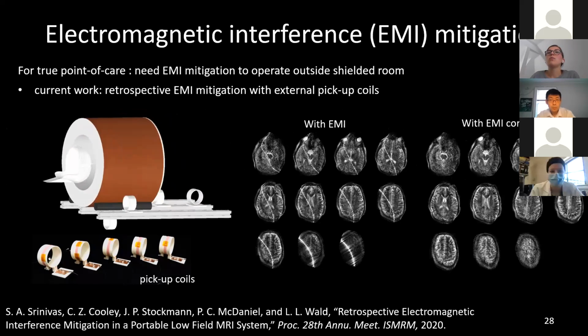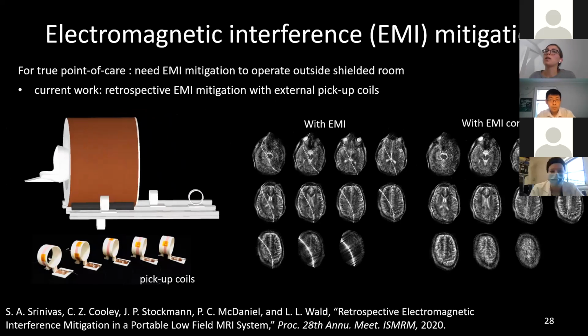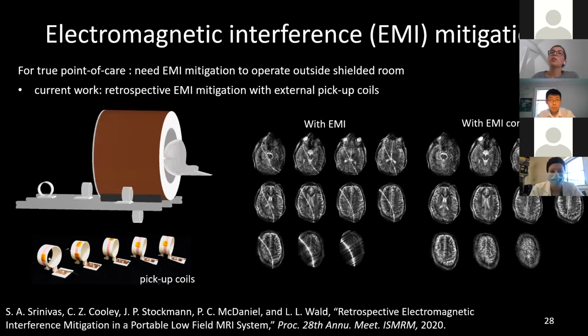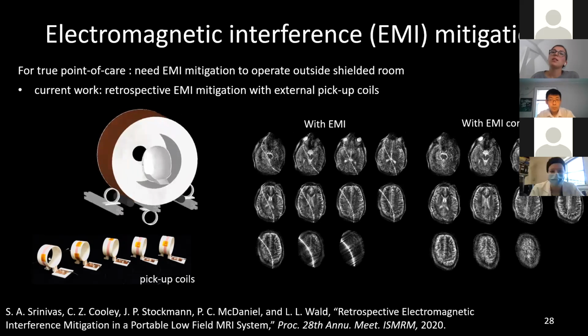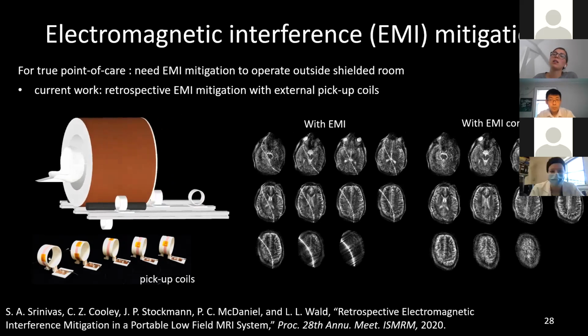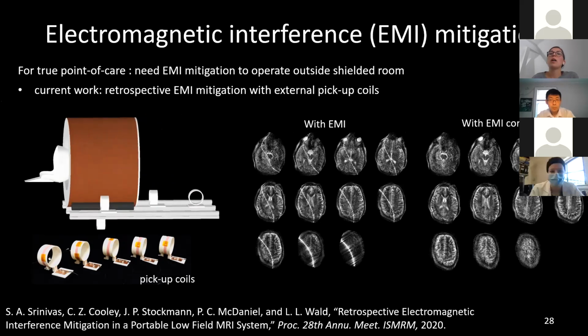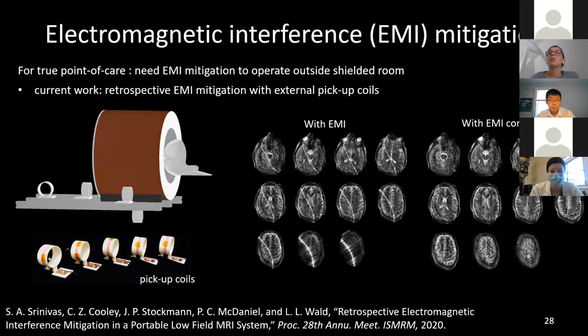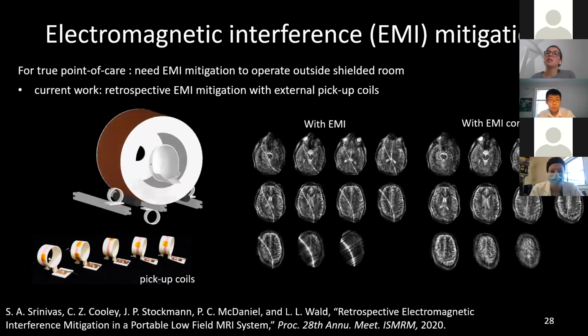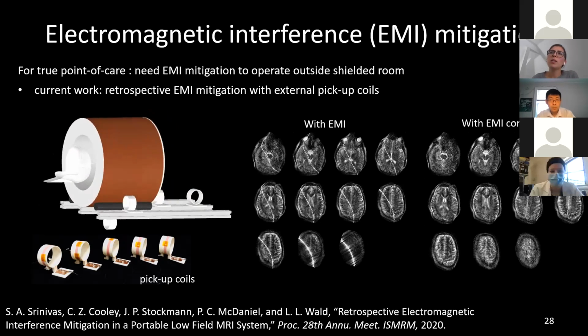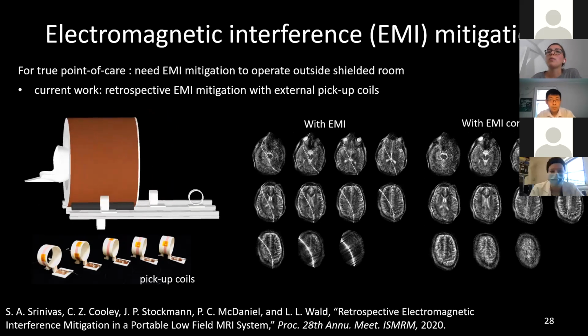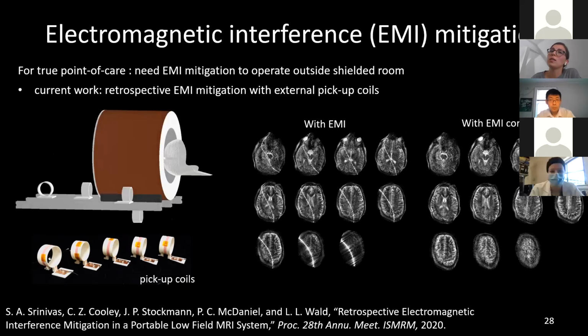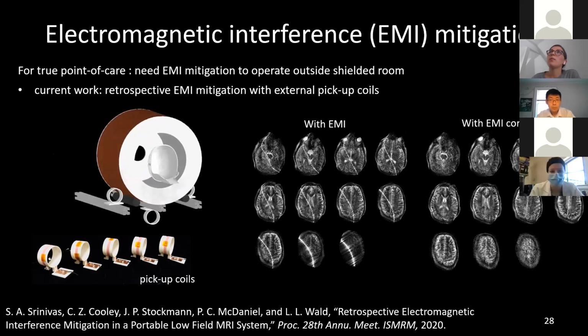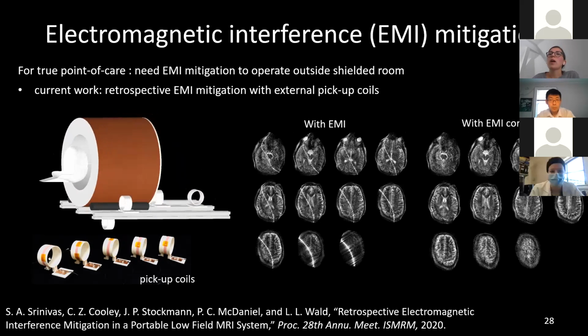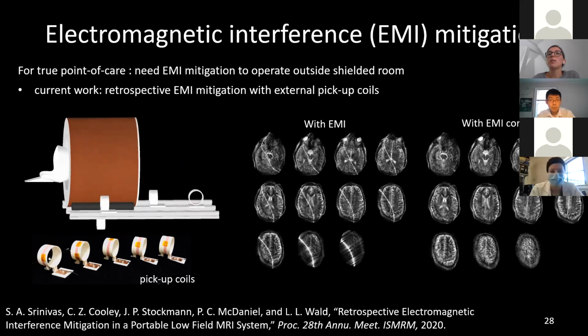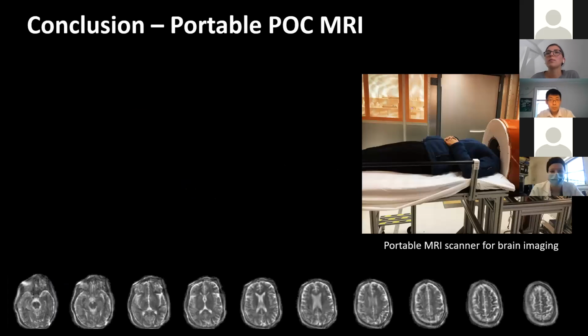So it comes down to some mitigation method for electromagnetic interference. So we're working on a retrospective method where we use these external pickup coils that we position around the magnet to measure external electromagnetic interference and then retrospectively remove those signals from the image. And I'm showing some preliminary results here with the image in the middle with EMI. You can see this streak down the middle of the image. And this is from an EMI source that we introduced. And on the right, I'm showing what the image looks like with our correction method. So we're making progress on this.